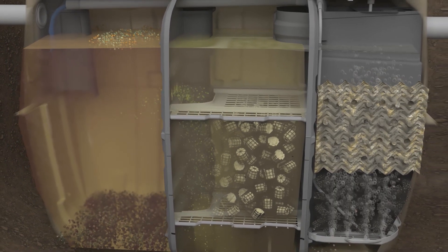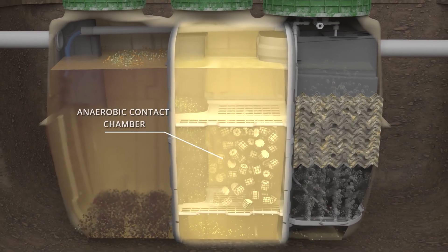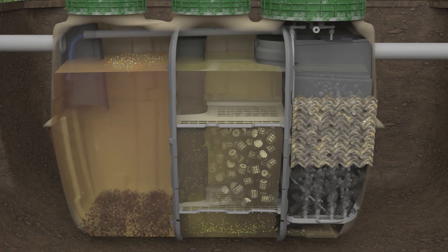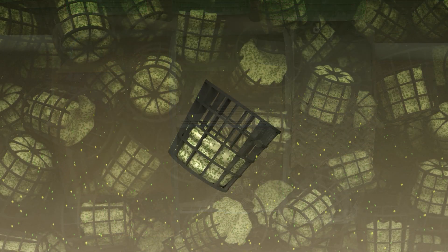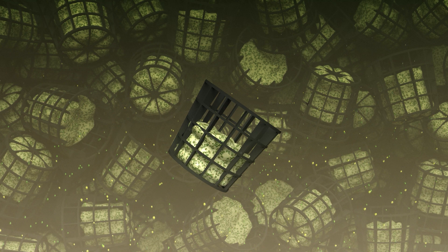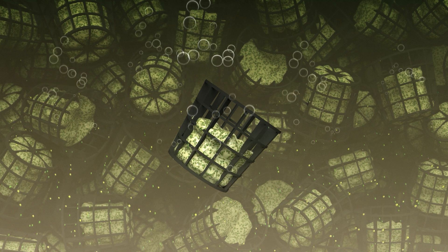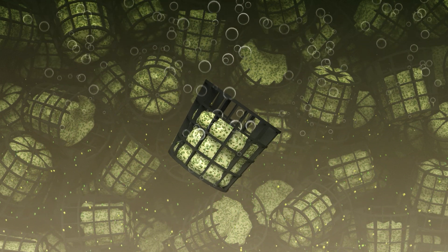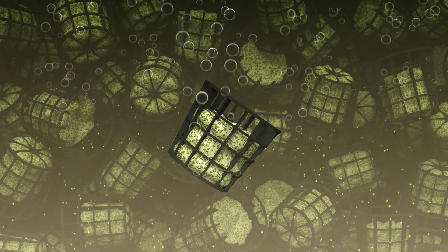The conditioned influent is directed downward through the baffle to the bottom of the second chamber, the anaerobic contact chamber. It then flows up through basket-type plastic media hosting millions of bacteria colonies. Here, organic matter is decomposed or captured by living microorganisms, and nitrate ions are reduced to a harmless gas.